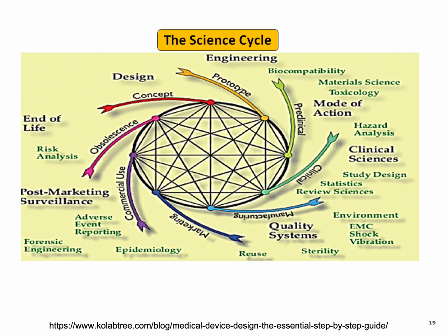We talk about the design input, design process, design output. And then based on the case that we saw, we can talk about making a prototype. So the engineer is going to make the prototype, and then based on the prototype, we are going to test it. Now, it may be preclinical, it may be clinical. We look into the mode of action, we look into any hazard analysis, we are going to create clinical evidence, and we are going to look into whether this is the device that we would like to have, and then we go through the manufacturing.